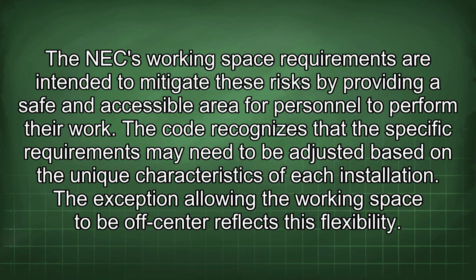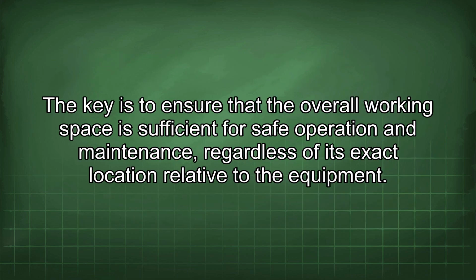The NEC working space requirements are intended to mitigate these risks by providing a safe and accessible area for personnel to perform their work. The code recognizes that the specific requirements may need to be adjusted based on the unique characteristics of each installation. The exception allowing the working space to be off-center reflects this flexibility. The key is to ensure that the overall working space is sufficient for safe operation and maintenance, regardless of its exact location relative to the equipment.